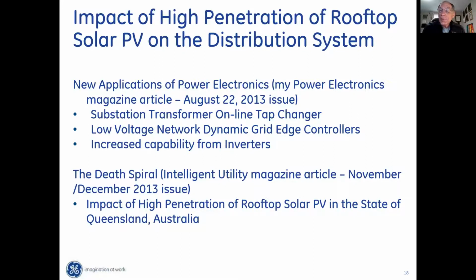This poor tap changer was going crazy, operating very frequently to keep the secondary voltage constant because of the tremendous increase in volatility of the primary voltage. It went from operating 5 to 10 times a day to 120 to 150 times per day, and its expected lifetime went from 35 years to less than 2 years.